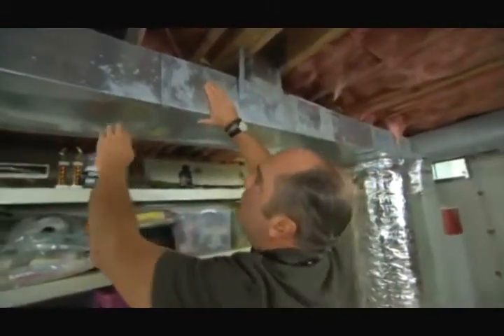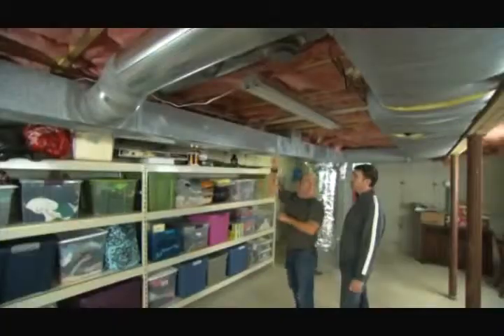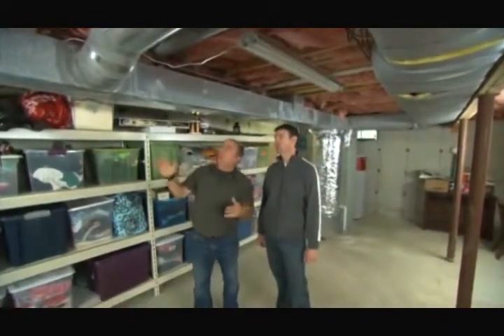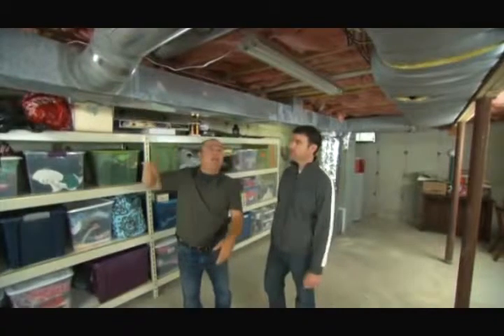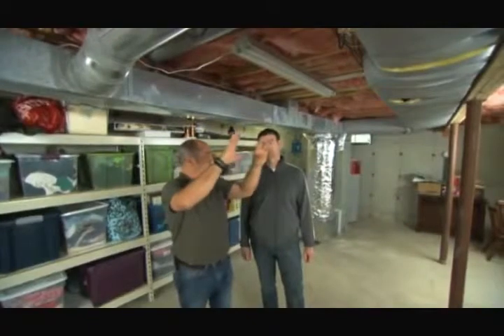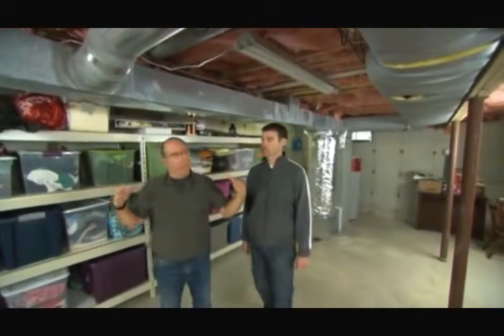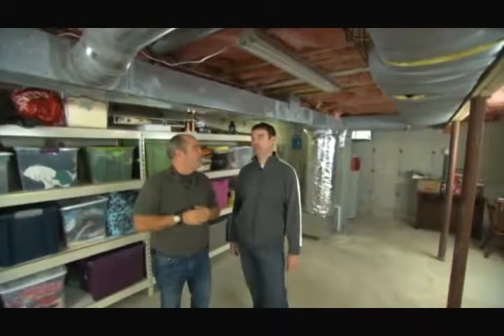The challenge: you've got metal trunks held together only by a metal cleat, and that's not airtight. We could try to seal the ductwork from the outside — on the return side it's straightforward, but on the supply side you'd have to pull down the insulation, seal the ducts, and re-insulate. And even then, a great percentage of ductwork is up inside the building where we can't get at it. So what I actually want to do is show a technology where we can seal every bit of this ductwork perfectly from the inside.